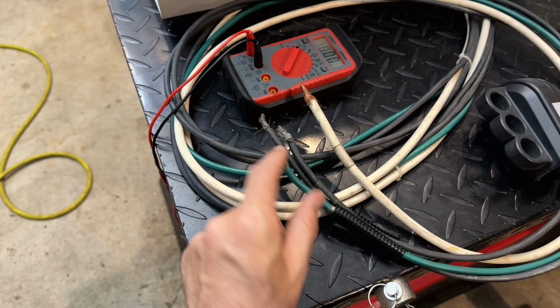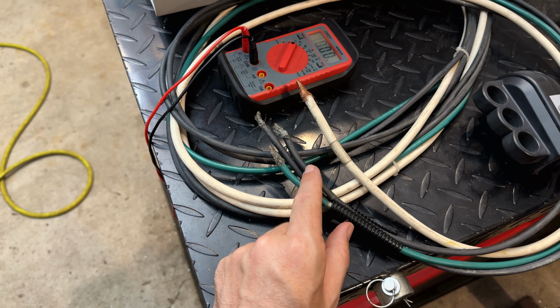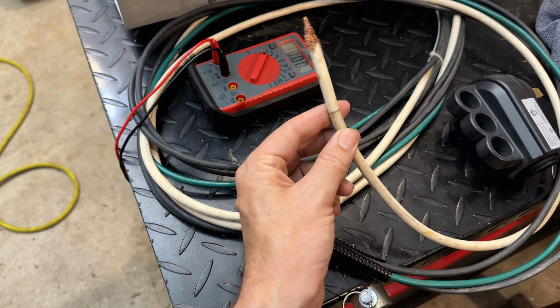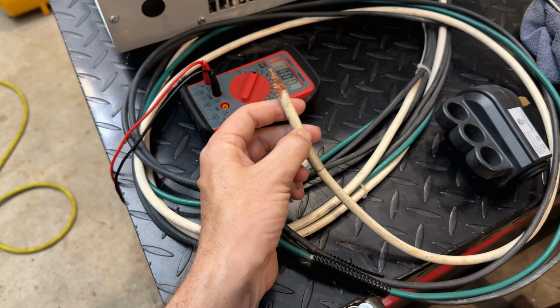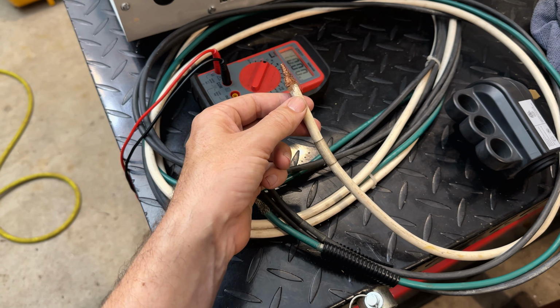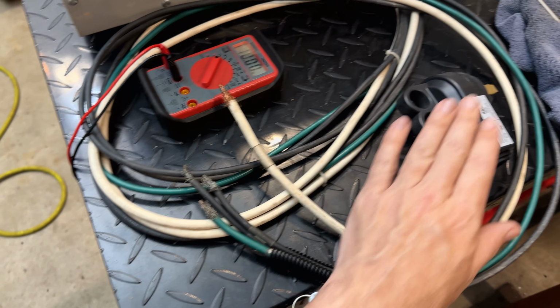Whereas in 240, which is how I'm going to wire it, half the current is going to flow on each of these legs, and with a balanced load, nothing should go on the neutral, or at most half load. So let's see if we can get that to fit in there, and then we'll try to power it up.